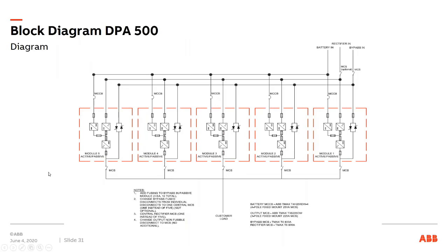So this is what the single line looks like. Actually, all of this is a 500 kW modular scalable UPS, fully populated. So in this one, there are 5 of the 100 kW modules. You close the door and it operates like a 500 kW. It'll support 500 kW any day, all day long. That's what it's designed to do.